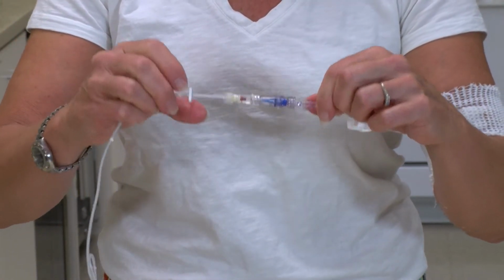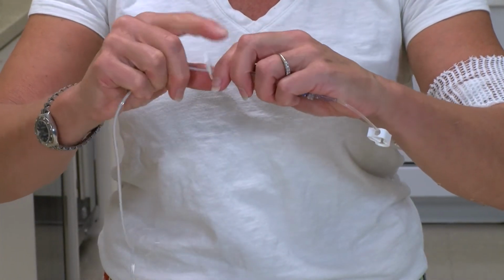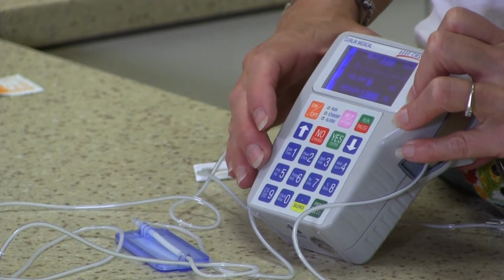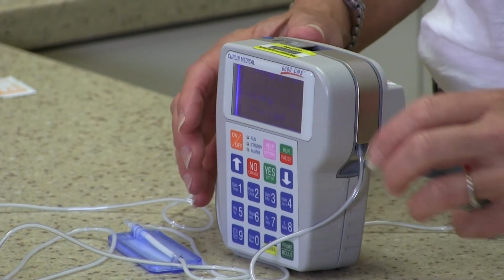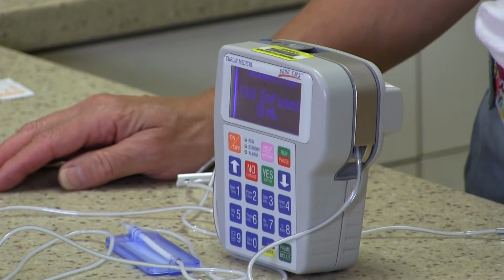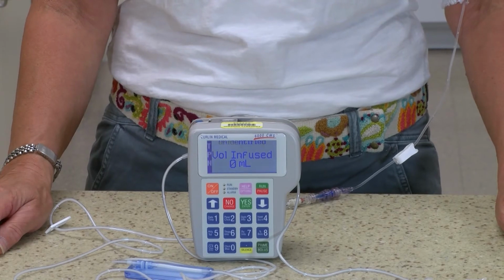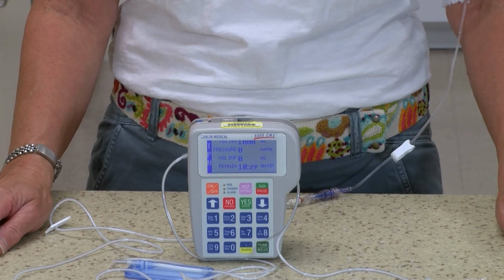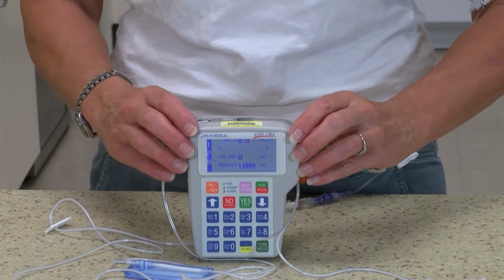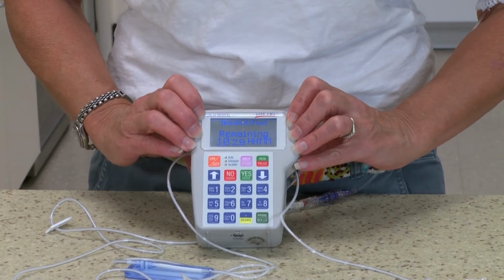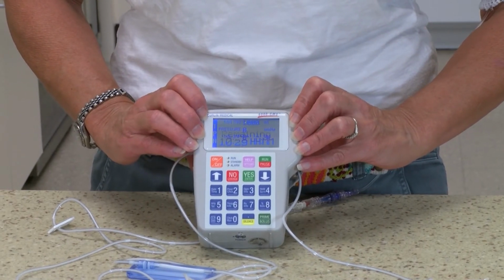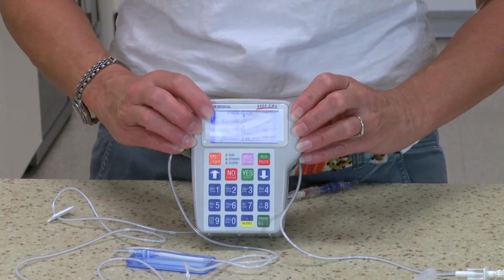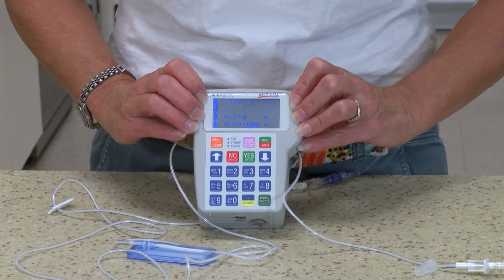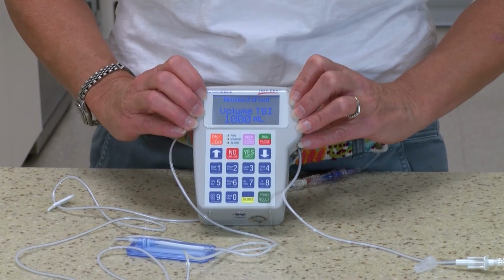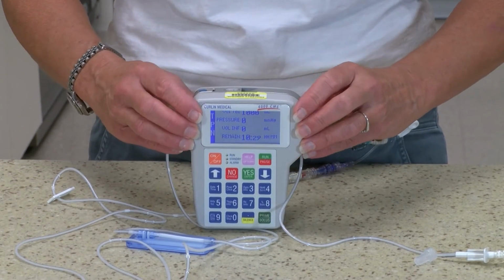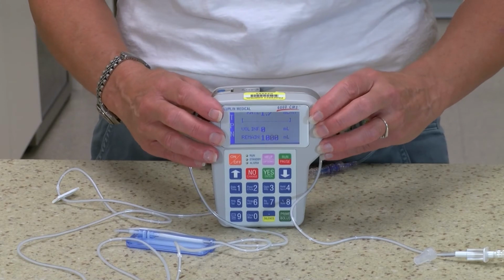Now unclamp the PN tubing and start the pump. For infusions that are not running for 24 hours, the pump is programmed to ramp up or increase its rate to the ordered rate for the first hour, and then it will ramp down or decrease the rate automatically for an hour at the end. If your PN runs continuously day and night, the pump will remain at a consistent rate at all times.